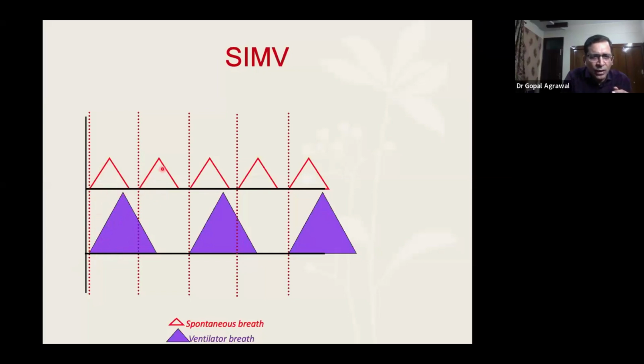This breath is unsupported because the machine is already giving a breath, and in exhalation mode, this breath by the baby is not detected by the machine and is not supported. So this is a supported breath. Again, this is a supported breath. This is a supported breath. These two are unsupported breaths. The machine is delivering at fixed rates. So this is supported, this is unsupported.